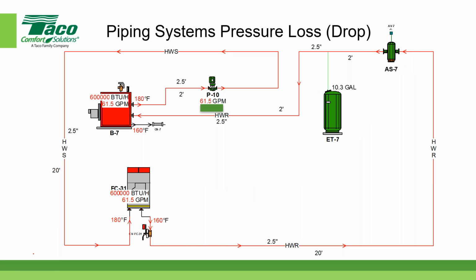Bryce just wanted to point out that lower velocity can also lead to miscellaneous impurities settling out in the pipe. That's a good point. Yes, a very good point as well. And Michael is making a statement, and you and I need to get a little more up to speed on this. For energy conservation, ASHRAE provides recommended standards for maximum pipe velocities and flow rates based on pipe sizes, hours of operation per year, constant versus variable speed, noise sensitivity, and so on.